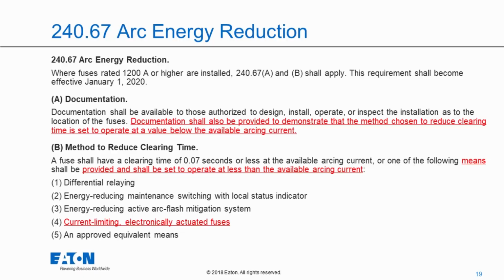It's just to where we have those larger ampacity fuses, because what happens is when we have large ampacity, either fuses or circuit breakers for that matter, we might have available fault current and arcing current that is less than the current limiting threshold of the fuse or perhaps the instantaneous trip of the circuit breaker. And that can cause delayed tripping under fault conditions, which can then result in high arc flash hazards. So what we're trying to do is address that issue, that if we have the case such that the available arcing current would result in delayed tripping, we want to add some sort of technology to provide faster clearing time and then obviously reduce the arc flash hazard.